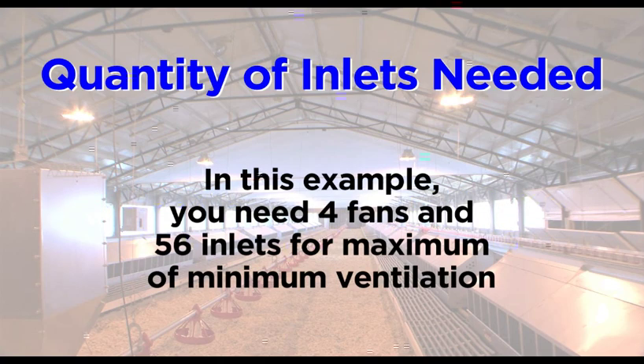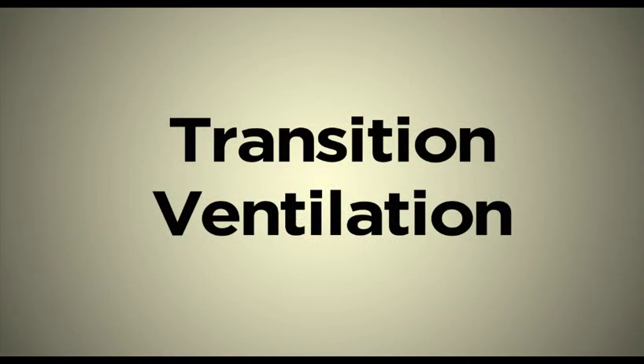You need to spec inlets 25% higher to prevent inlets from ever reaching 100% of capacity. 45 inlets times 125% equals 56 inlets. For minimum ventilation, these will be lighter weighted inlets. In this example, you need 4 fans and 56 inlets for this house for maximum of minimum ventilation.